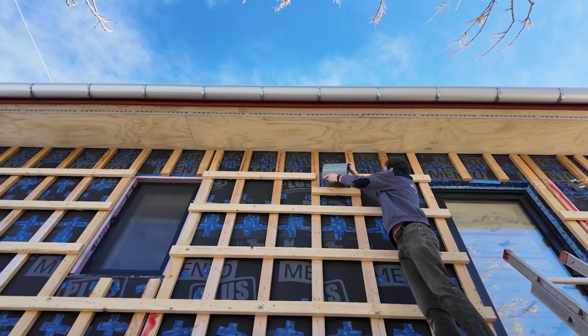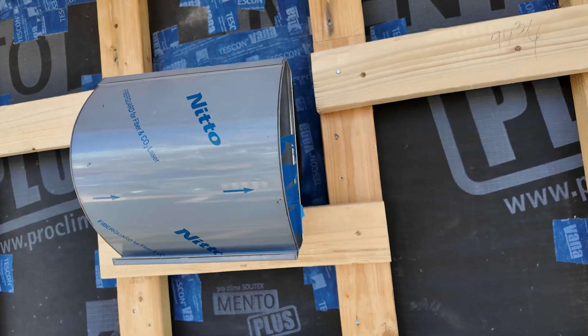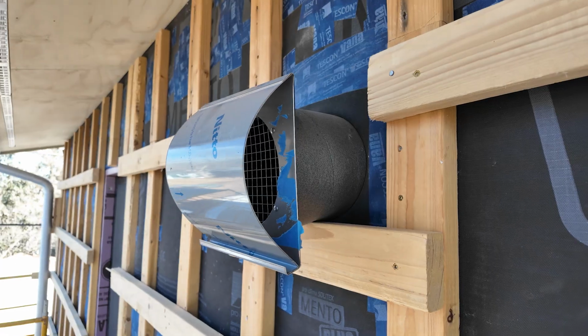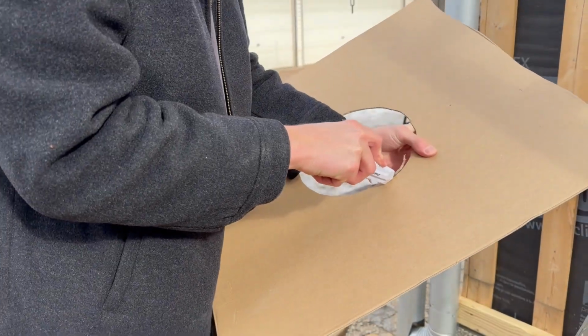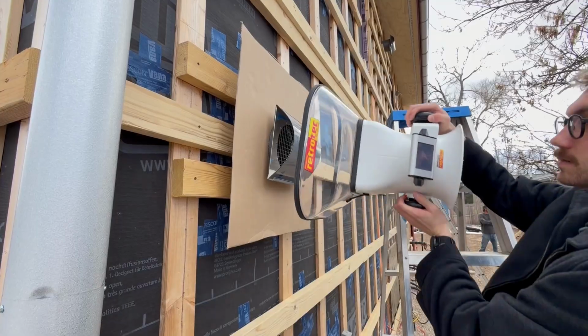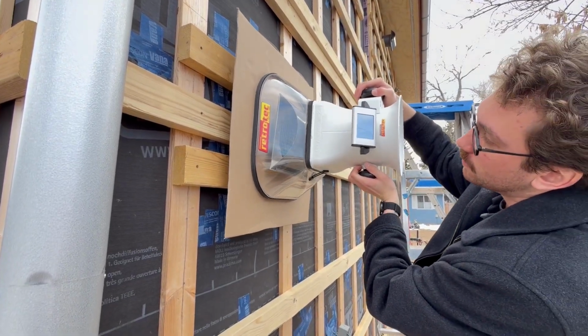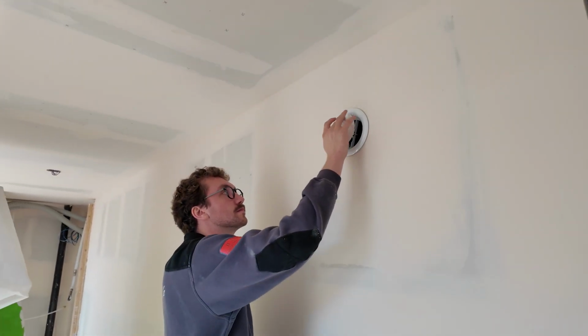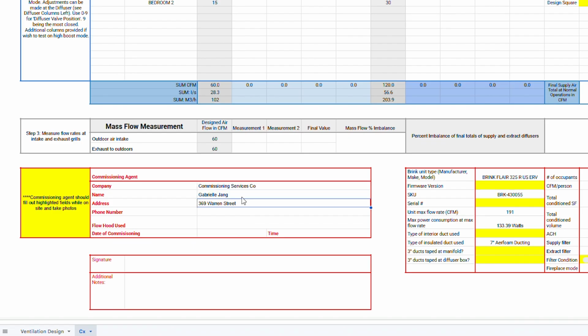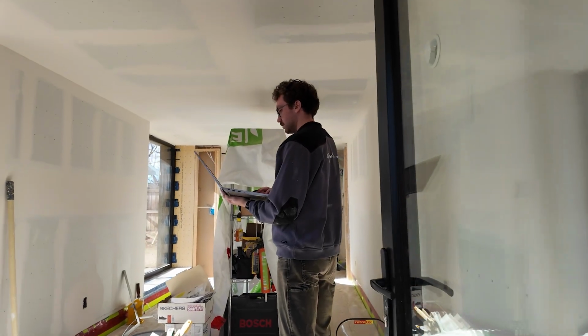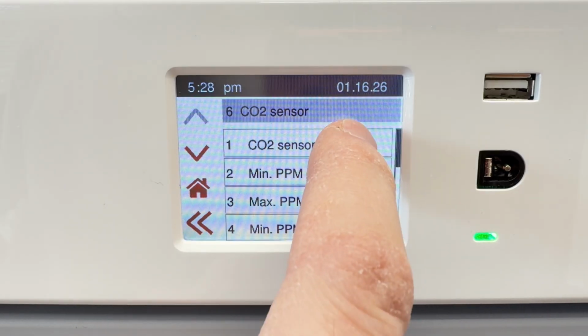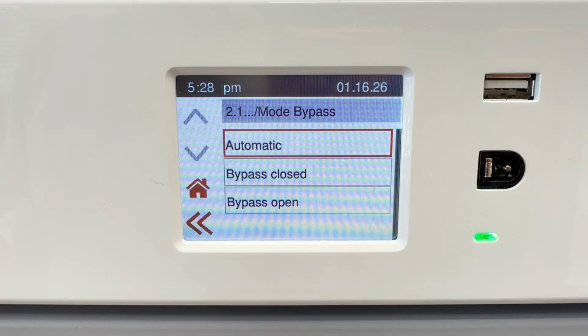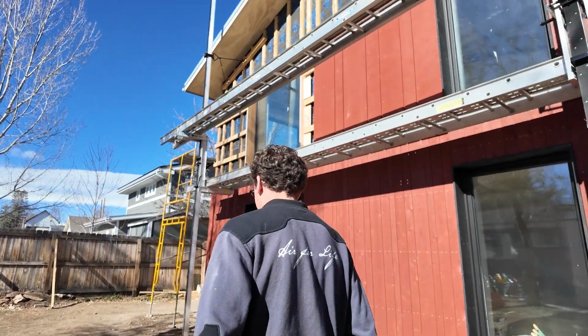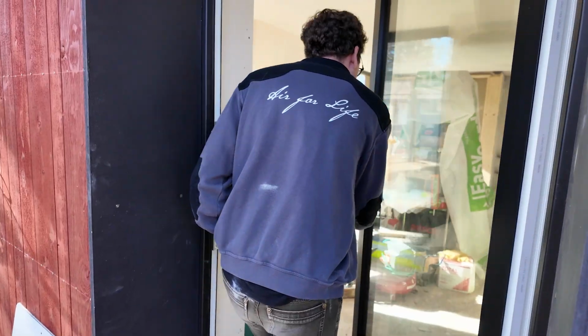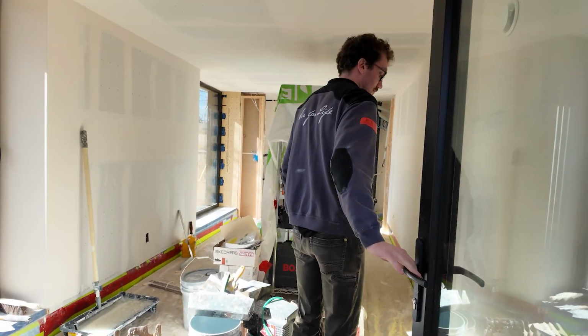Certain building certifications require measuring the airflow at the intake and exhaust of the unit. Depending on the exterior siding, some creativity may be required to create a seal between the flow hood and the grill. Once all design flow rates have been achieved, the commissioning agent should sign off and provide the report to all applicable parties. With commissioning complete, all external controls such as CO2 sensors and the bypass should be turned back on. The commissioning agent often assists with any accessory controls that are installed, ensuring all are working correctly.